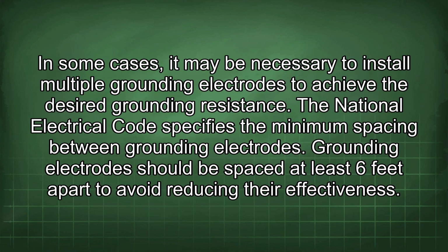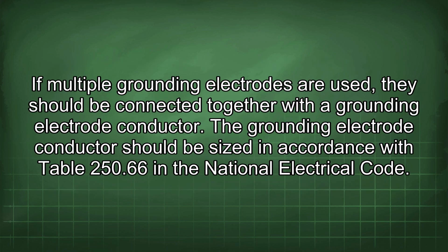In some cases, it may be necessary to install multiple grounding electrodes to achieve the desired grounding resistance. The National Electrical Code specifies the minimum spacing between grounding electrodes. Grounding electrodes should be spaced at least 6 feet apart to avoid reducing their effectiveness. If multiple grounding electrodes are used, they should be connected together with a grounding electrode conductor. The grounding electrode conductor should be sized in accordance with Table 250.66 in the National Electrical Code.